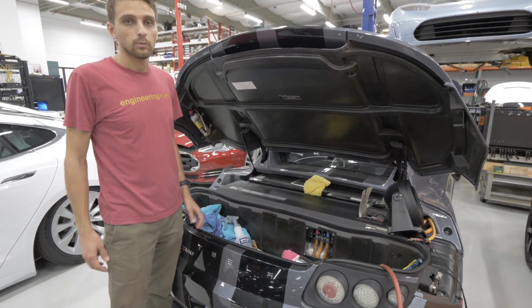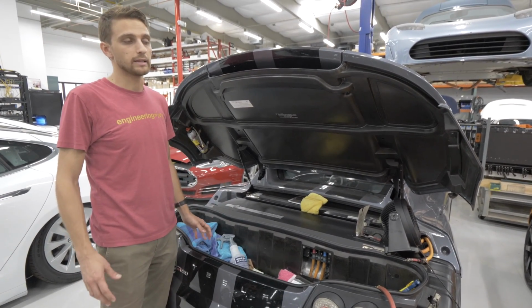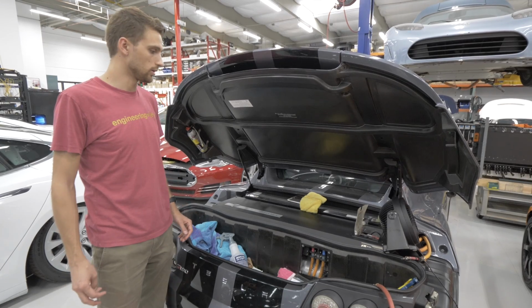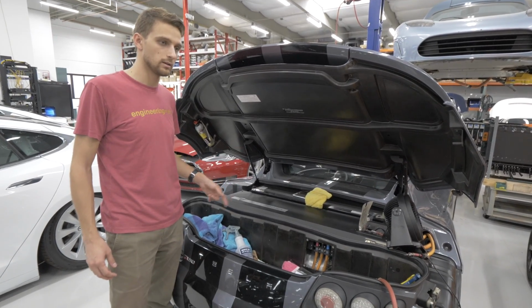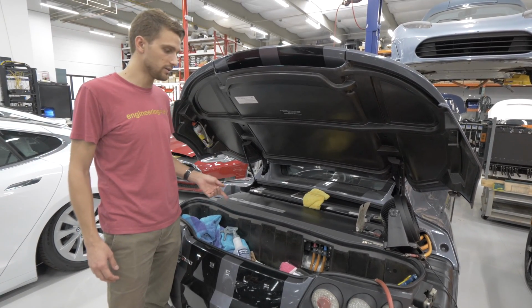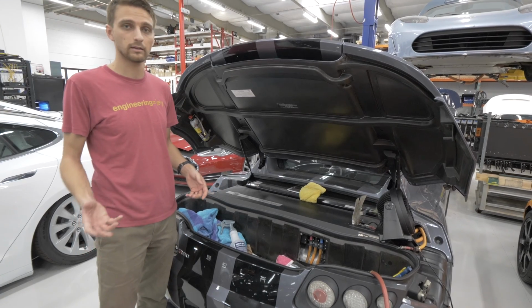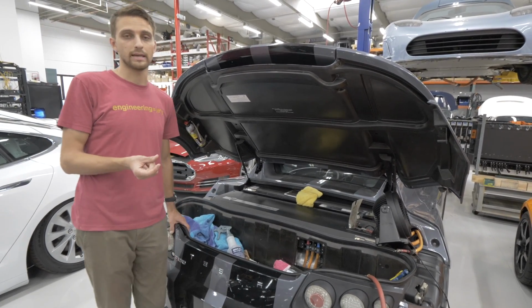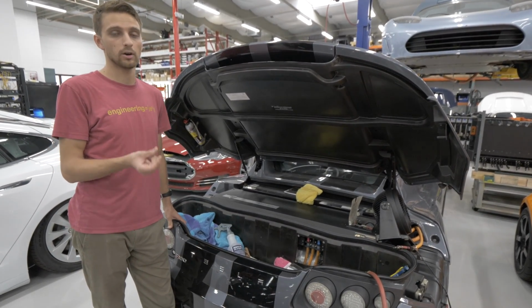When that happens, the temperatures get higher and you'll likely have power limiting problems, or find the fans running more often. When the fans run more often, it's a negative feedback loop, and your fan connector can burn out in that scenario.